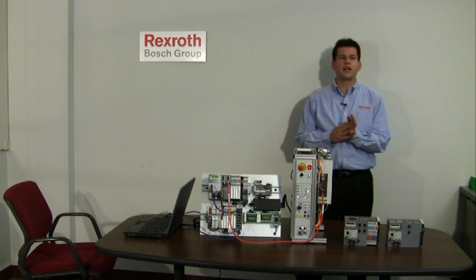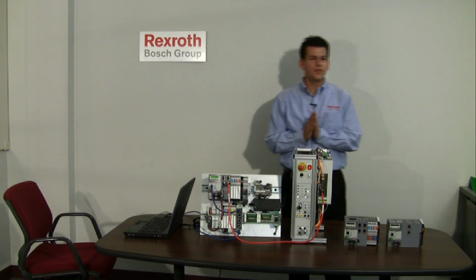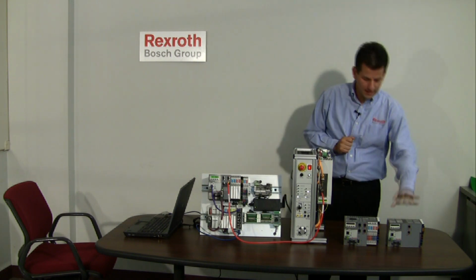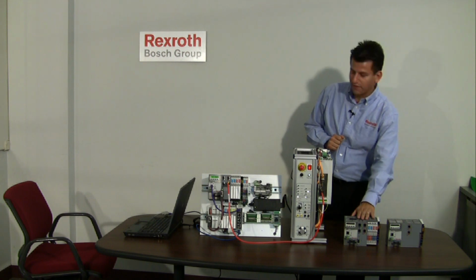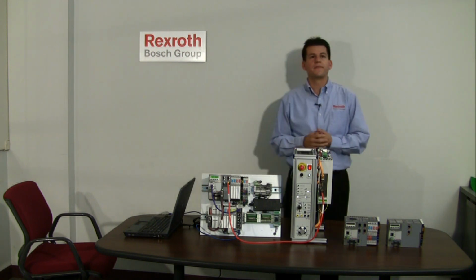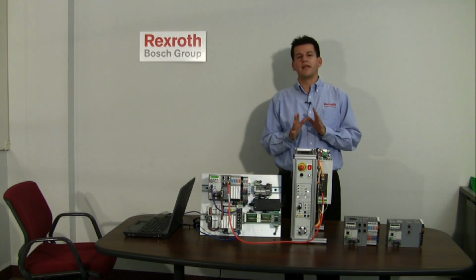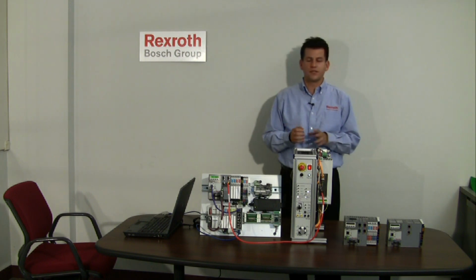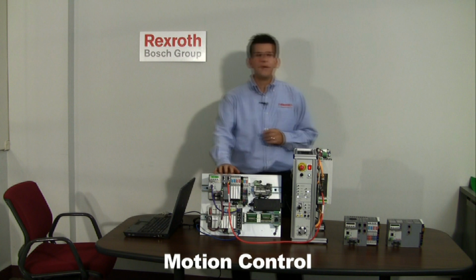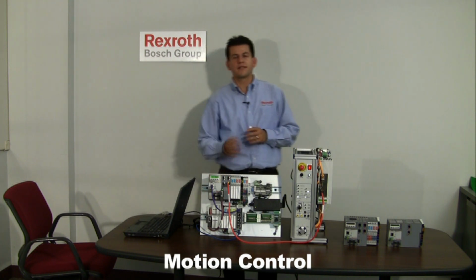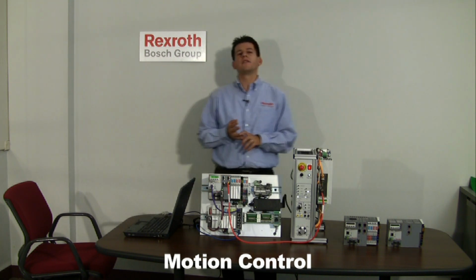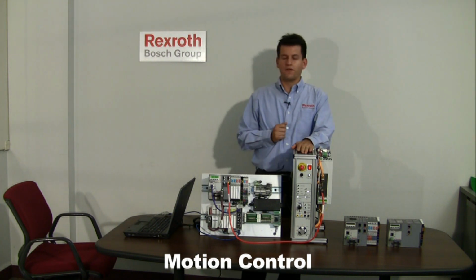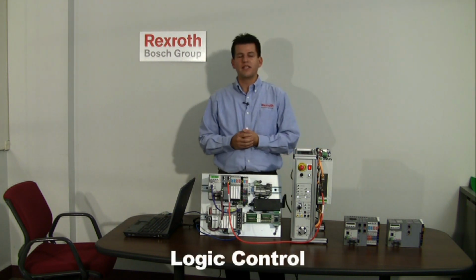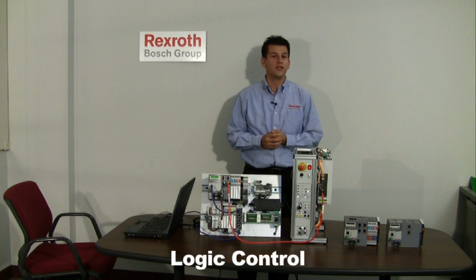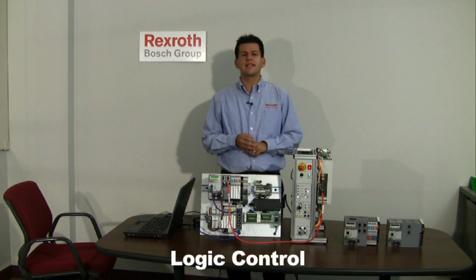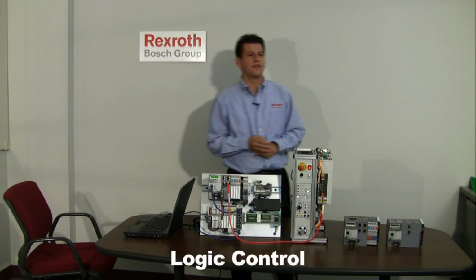Its compact control architecture is based on a scalable IndraControl L platform with an L25, L45, and L65. It's a complete and universal automation solution for all applications with motion control. With an integrated motion kernel for axis synchronization for linear and non-linear motions for up to 64 drives. Logic control, integrated multitasking PLC kernel, IndraLogic, according to IEC 61131-3 standards.